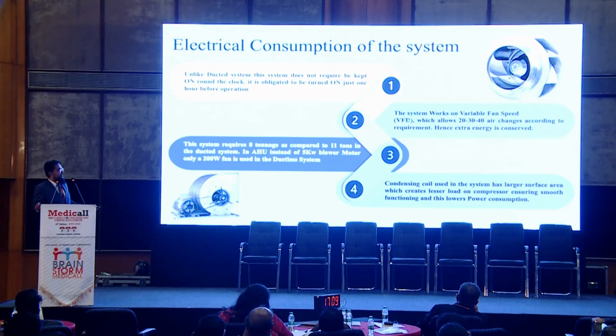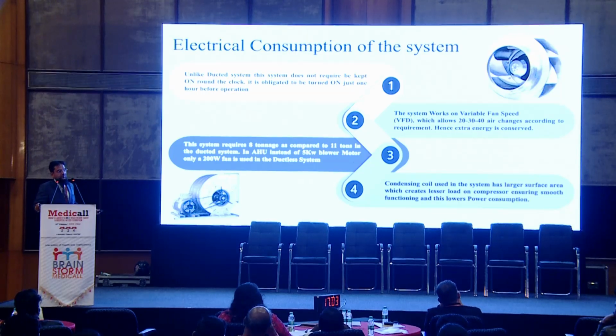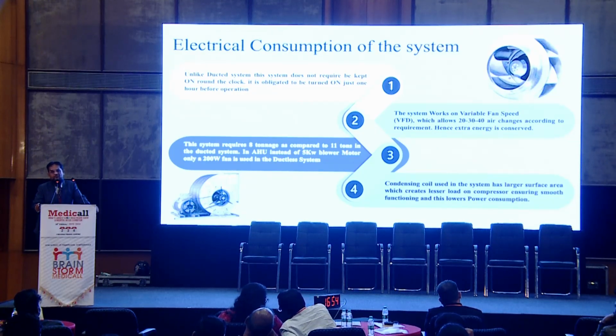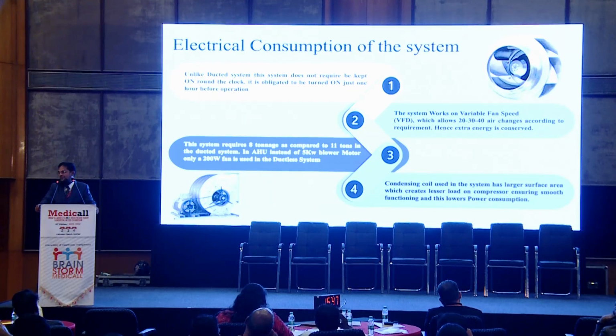Then VFD had been given, so we can give 20, 30, 40 air changes according to your requirement. If I give 40 air changes instead of 20, what will be the benefit? One thing is that with 40 air changes, within 15 to 20 minutes the air quality of your OT will be achieved, and you can take your patient in within 15-20 minutes.